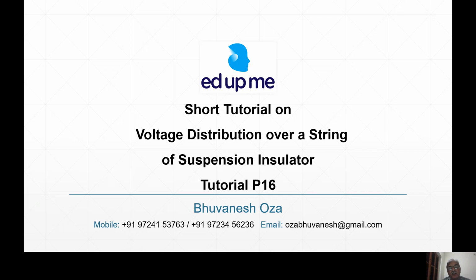There is a capacitance between a metal part which is not at 0 voltage. You see, the metal part between the first two discs near the high voltage conductor is not at 0 voltage. So between that and the grounded tower, there will be a capacitance formed. That is a stray capacitance. And when there is a stray capacitance, current will pass through it.